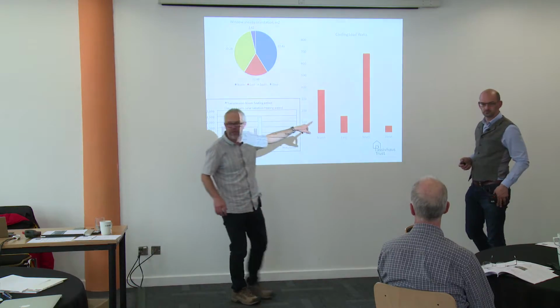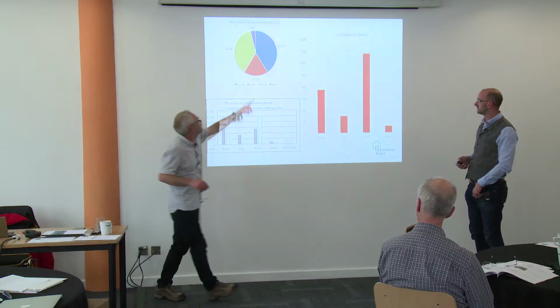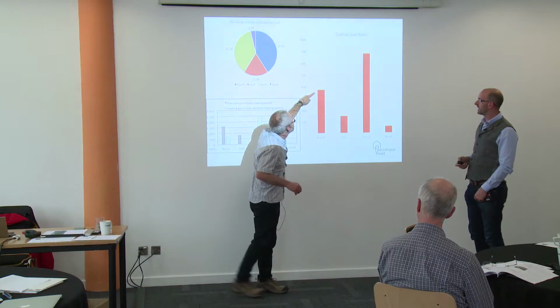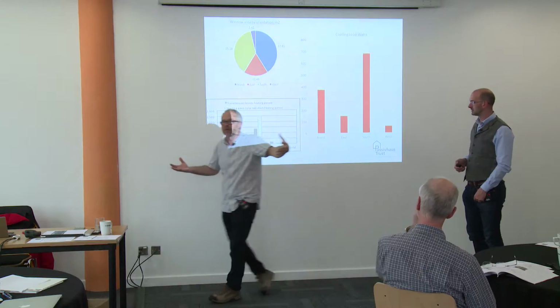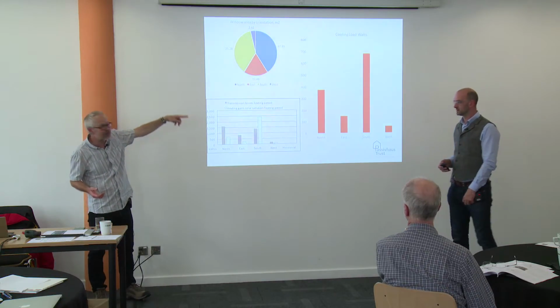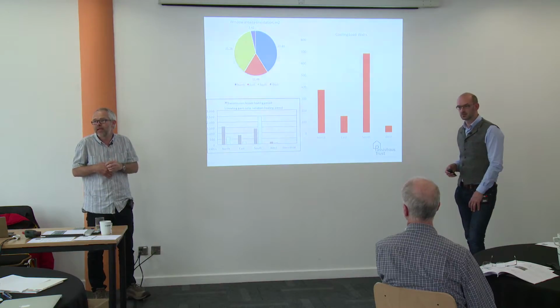So again, this is a graph that isn't in PHPP, but because it's a spreadsheet, you can hack it. The cooling load figures, or you can do it in kilowatt hours. So the north is significant. It's over half of what the south is. South you're expecting to be part of the heat gains. But the north, which you wouldn't think was a problem, is actually a significant part of the cooling load and not a useful part of the winter heat gains.